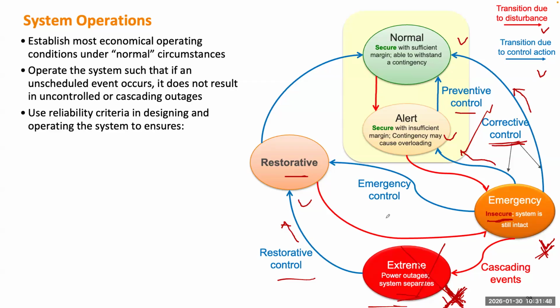You take a restorative control, or another option is you can do a more aggressive control, such as, I know the failure is propagating in this area, there's no way I can clear all the failure, so I just cut off this area to make it an island. Then the rest of the system will be protected. That can be considered emergency control. Emergency control means economic factors are not important anymore. You have to save the system as much as you can. You can take any action. If you don't take action, that's violating the reliability standard. So that's another, more aggressive control.